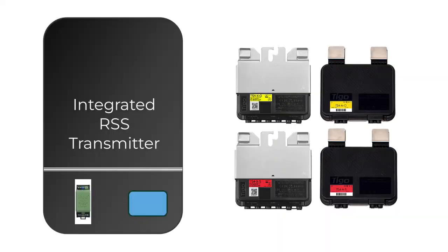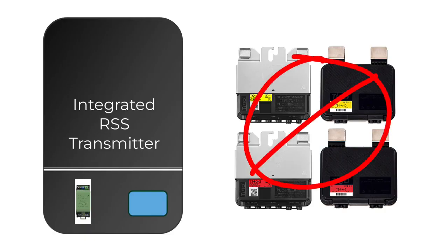It's unmonitored, and it uses power line communication to signal the rapid shutdown command. So if an inverter has an internal Tigo component, you need to make sure that it's a CCA if you're using the O and the S. If it's not, then you're going to have to get an external CCA.